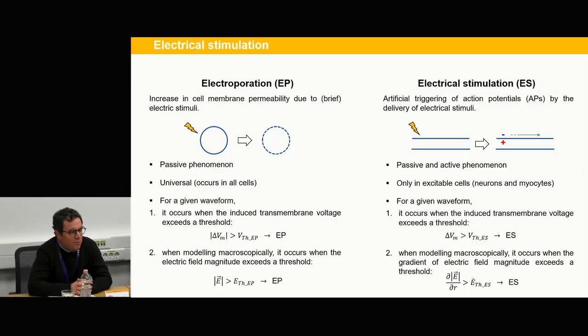The first thing everybody should be aware of is that when we are delivering pulses for performing electroporation, PFA, we are most likely going to cause electrical stimulation. The reason for that is basically in both phenomena, what we want to do is change the transmembrane voltage. That's what initiates both phenomena.